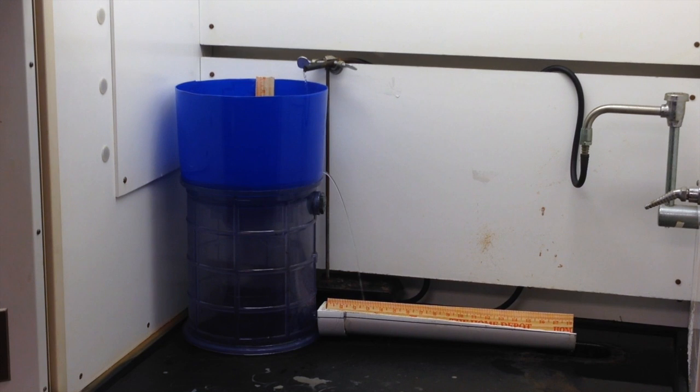So the flow rate of water into the distribution pan has a marked impact on the flow rate out of the pan, not surprisingly, and that in turn impacts the distribution of water over the nozzles and over the spray mechanisms coming out of the bottom of the downcomers in the distribution pan, that is critical to dispersing the water over the top of the fill pack.